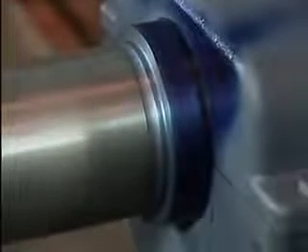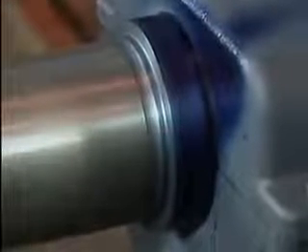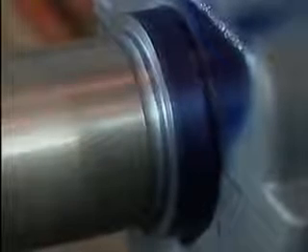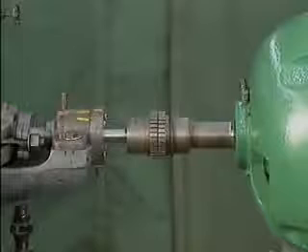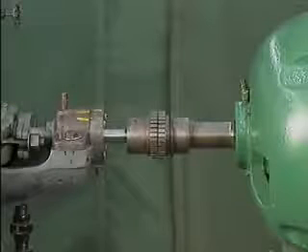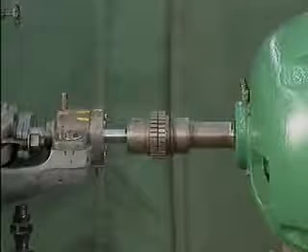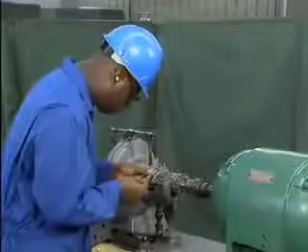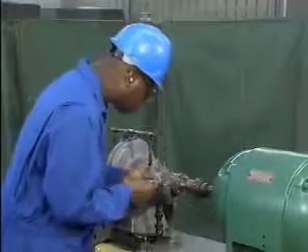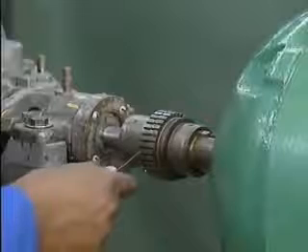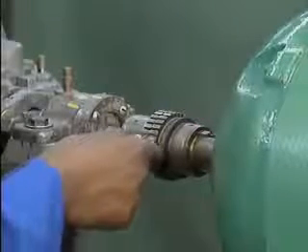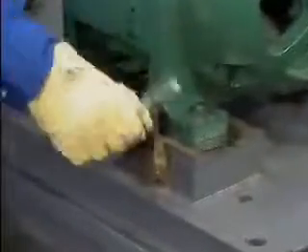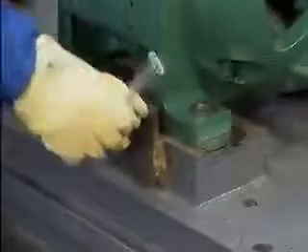Later, when the motor is shut down, the mark on the shaft can be lined up with the reference point to place the motor shaft at its magnetic center. Once the shafts of the components involved in an alignment have been positioned at their mechanical and magnetic centers, the coupling face gap can be set to its proper specification. This is done by inserting a feeler gauge the size of the ideal face gap between the coupling hubs and maneuvering the movable component until the proper gap is achieved.